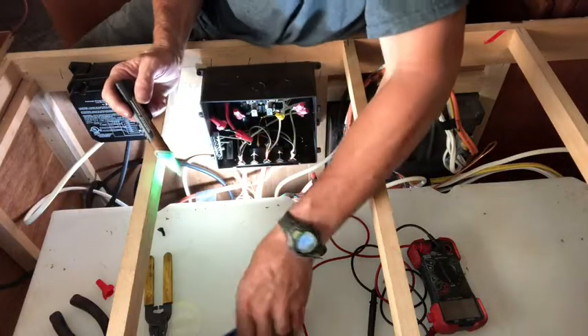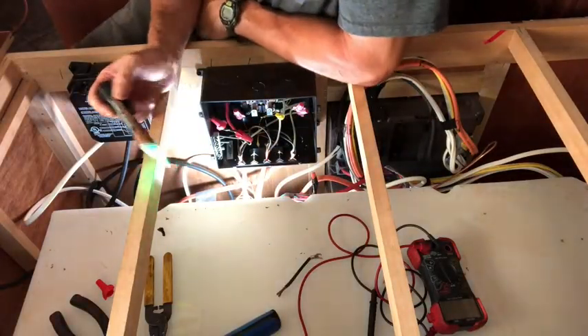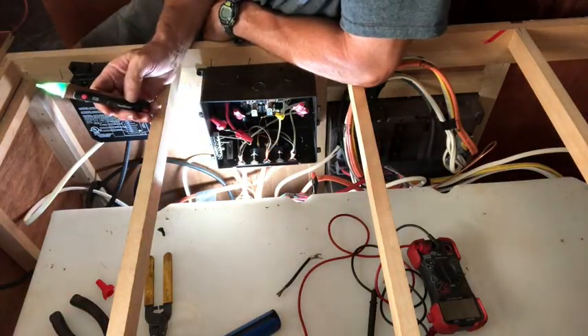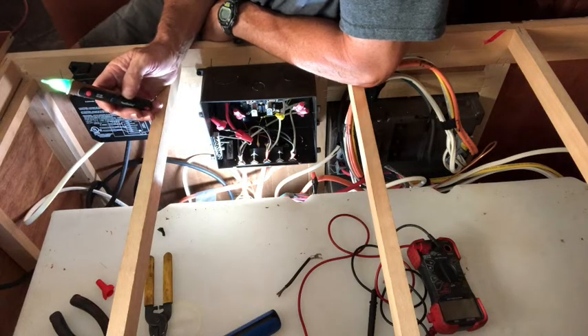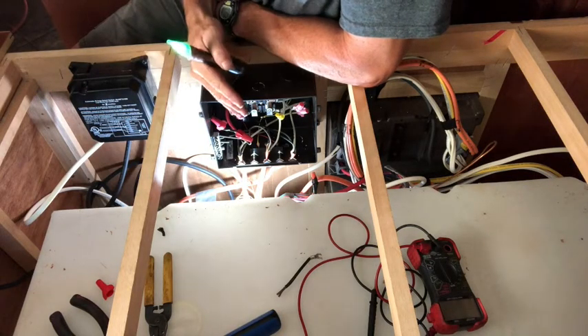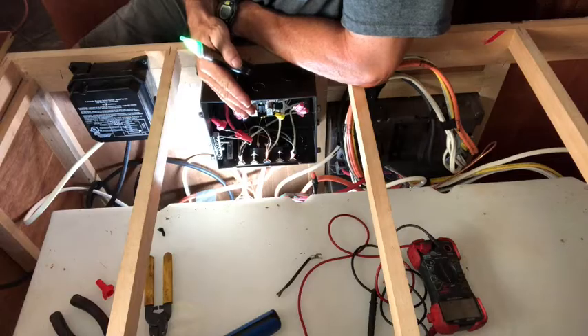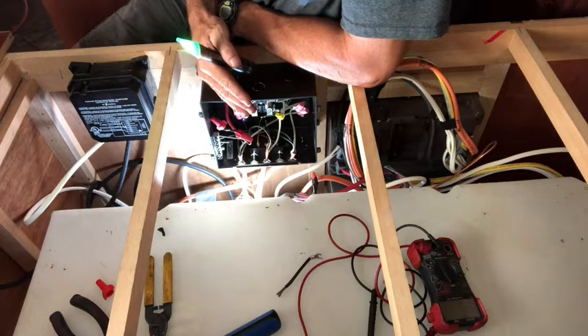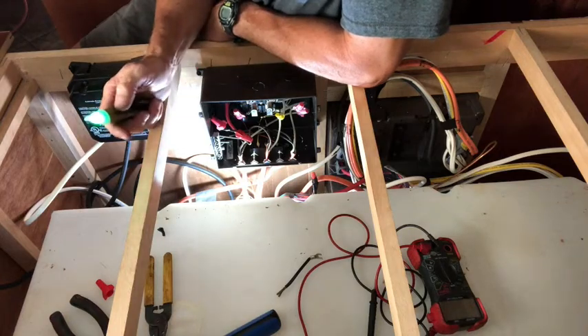So my transfer switch is not flipping properly, so I'm going to go ahead and replace that. The next step then is to remove all power that could possibly come into this box before I start taking wire nuts off and unbolting stuff. Things to check.